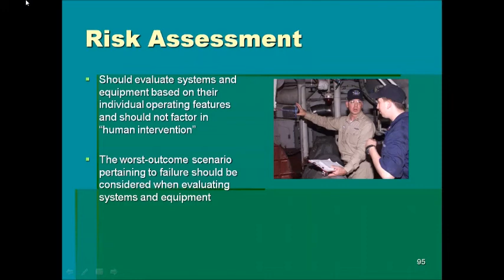And again, I could spend a full 8 hours talking to you about this risk assessment process, but neither NFPA nor CMS tells you how to conduct this process. Now, there are some tools that are out there that are accessible online and available through other measures, but in essence, you've got to make a 1 through 4 determination of what the failure of the system would be and what the consequences of that failure are. If the electricity in a space that you're going to renovate fails, and you speculate that the consequences of that failure can cause major injury or death to staff or residents or patients in that area, you would categorize that area as a Category 1.